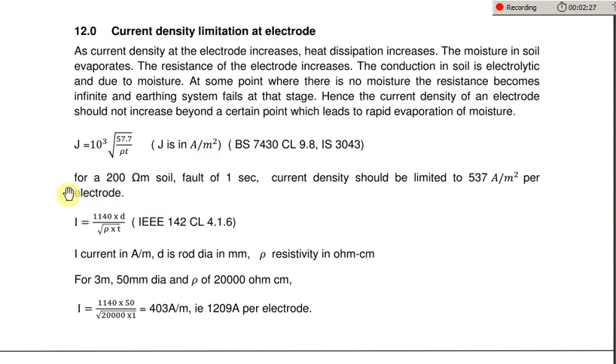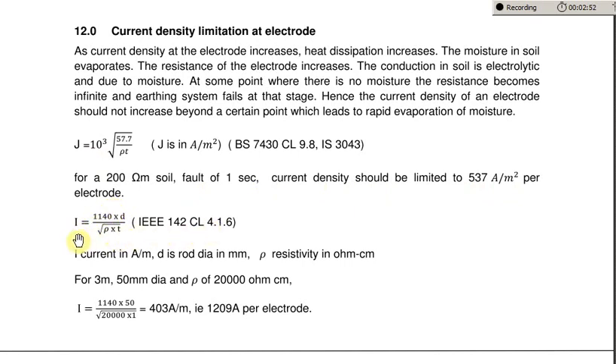For example, consider a soil with 200 ohm-meter resistivity and a fault duration of one second. We get from this formula the current density at 537 amps per meter square. Similarly, from IEEE 142 also you get the current density and you get around 1209 amps per electrode. But I prefer to use the first formula.